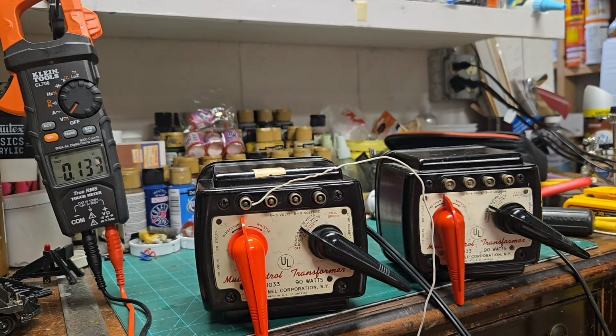16 gauge AWG - most transformers are set up probably like that ZW over there, that older post-war transformer, which does have a 15 amp fuse in it. The 16 AWG, for safety reasons, I'd say is plenty acceptable. It's all relative to the insulation, how long you run it, and how much amperage it will carry, but I'm going by a standard size layout here - just keep that in mind. So for 16 AWG, I'd say a safe amperage to carry is about 10 amps.